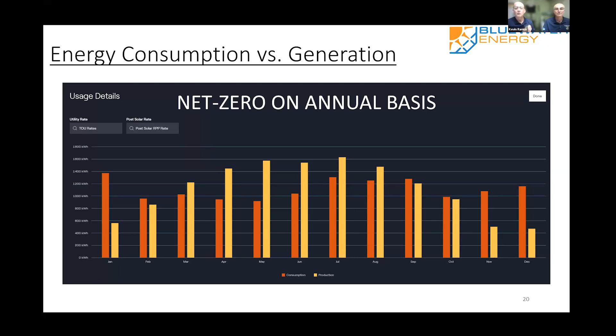Yes. Module manufacturers will specify that crystalline silicon, which is what the cells within the solar modules are constructed of, will degrade over time, and manufacturers will specify what level of degradation they expect from their product. Typically that's somewhere between 0.3 to 0.5% per year, and we factor that directly into the model. We factor in a 1% loss from degradation in our generation forecast. So again, we do model on the conservative side — we're not sandbagging here, but we do want to make sure we're not providing a solution that overstates what it's actually going to be able to deliver.